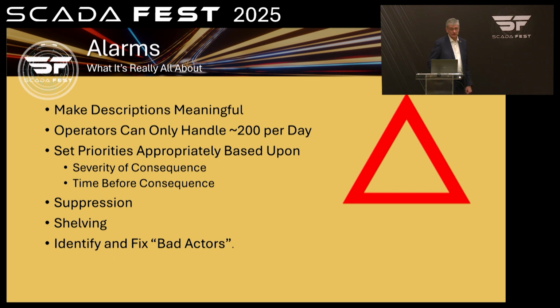Got to find the bad actors. I've seen systems where you go in and see what are the bad actor alarms. There's a report in the alarm page that shows you the bad actors - those are the ones coming on an awful lot. If they're buried among the other 100 alarms you're getting a day, it may not be obvious which ones are coming on frequently. Some operators might start to recognize them and say, oh, that's that one again, okay, we won't even worry about that one. But you got to find those alarms to stop that operator from tuning out.